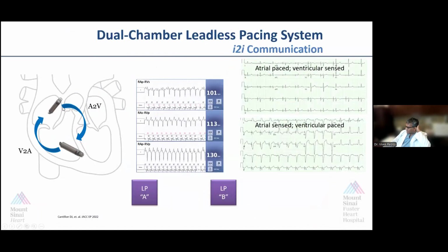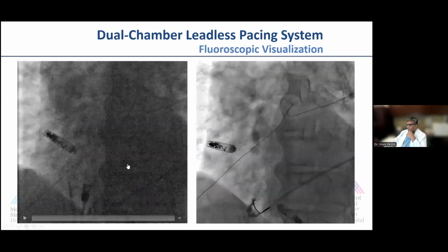So the idea here is to have two devices, and they have so-called implant-to-implant or i2i communication. With each paced or sensed event, there's an impulse that's encoded into the QRS complex or P wave that's sent, and then the other device detects it. It's all conductive communication. With each pacing and sensing, it's constantly communicating back and forth, which is very impressive. By the way, that also has an impact on battery drain, which we can also talk about.